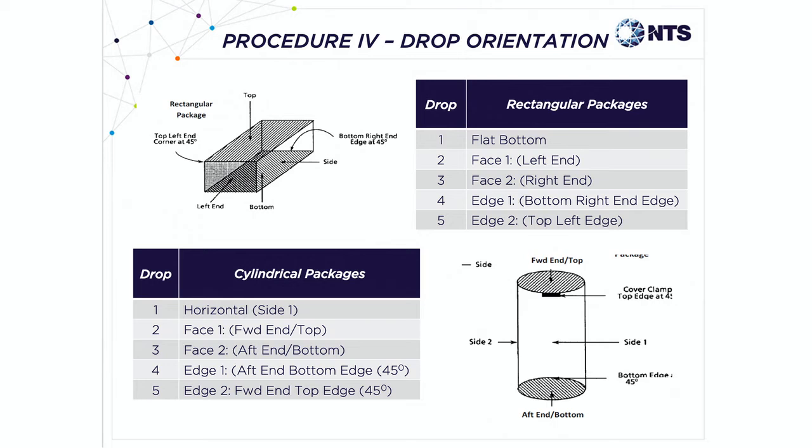One interesting thing in the document that some people don't take advantage of is that a box isn't really designed to take these 26 shocks all at one time. I mean, obviously, if it does, you need a new shipping container, right? But in general, you can use up to 5 different units if you want to get through this test. I know logistically or financially that could be a problem, but it does allow you to change out units during this 26 drop logistic test.